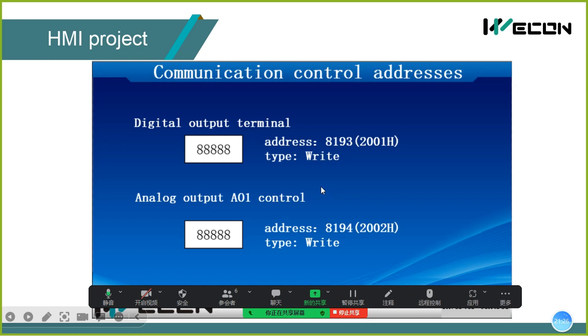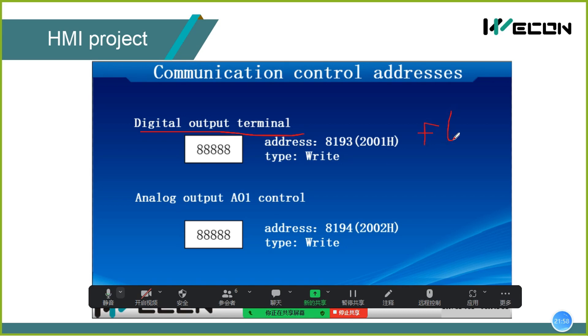Compared to the test program on our website, I added this page. For example, when the inverter communicates with HMI and I want to control Relay 1 digital output terminal, I first need to set F6.0 to 20, and then set bit 1. Assign the binary value 0100 to this address, which is the same as assigning the decimal value 4 to this address.